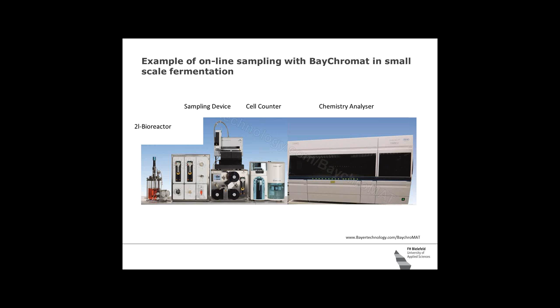And there are also other companies that provide those setups, but they all have certain downsides because the consumption of sample volume is now very, very interesting. Because why would you spend the money on an automated sampling device to draw sample more than once a day, like every hour, every 2 hours? And it's not only the sample volume that is being used for the analysis, it's also the sample volume that is necessary to flush the lines. You want the sample to be representative of what is in the bioreactor.